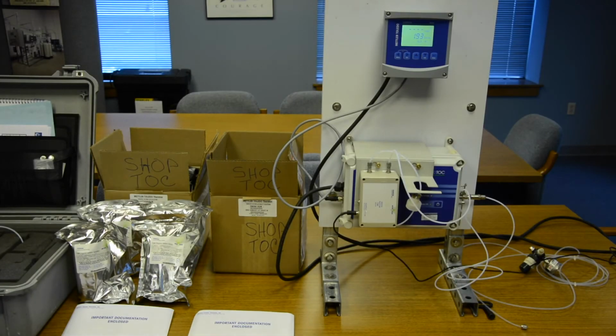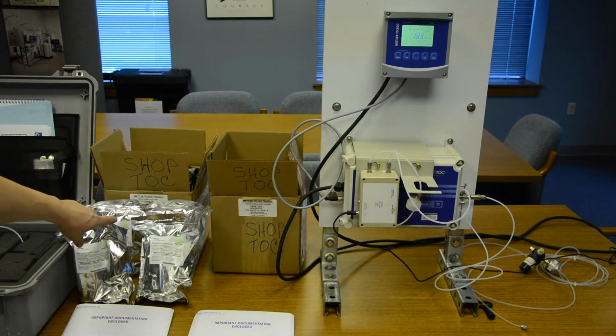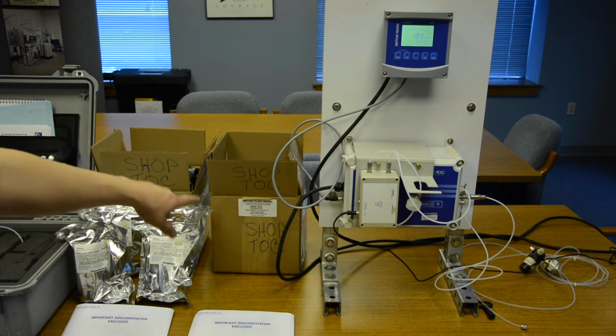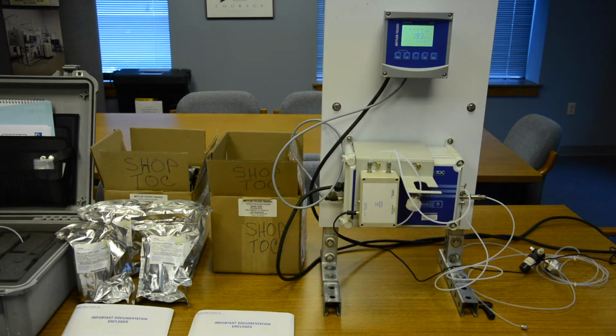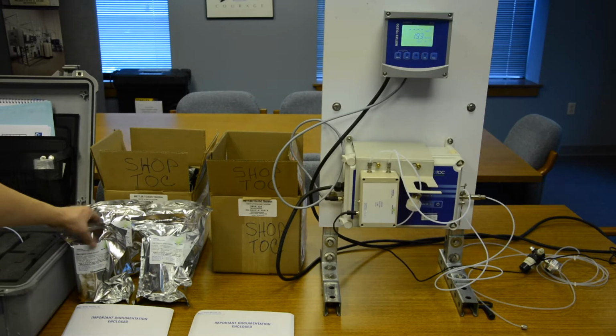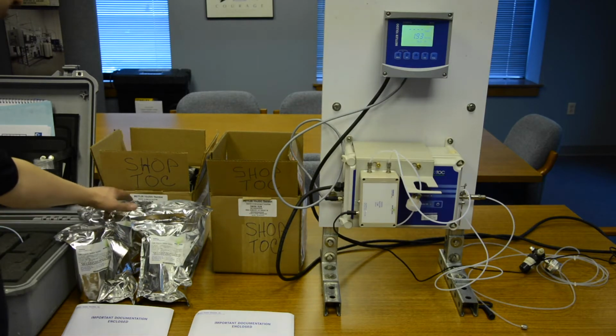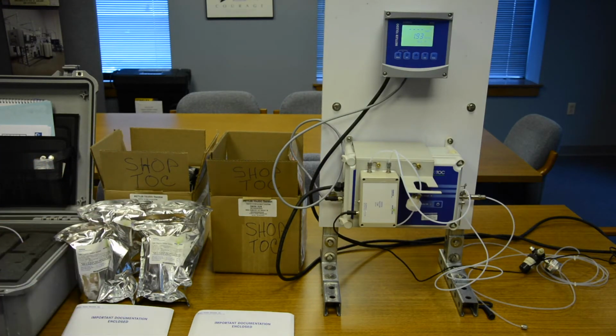Now with the calibration, we have two different kinds of calibration solutions. The first one is the actual calibration solution when we do the calibration. The second is a suitability solution that we use to make sure and verify that the unit is properly reading different kinds of TOC levels. So in the first kit, we have 4 solutions. We have the 2 solutions that are considered blank water. That's water that we can use that's low parts per billion, but we can use it to test the pump or other things. It's not integral in the calibration process.